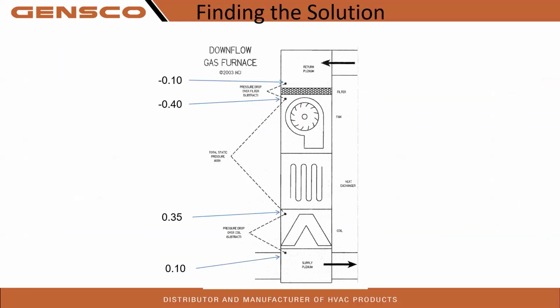Finding the solution. So we got a downflow gas furnace, right? So these are ideally what we want to see. So total external static pressure is 0.75. We could have symptoms, could be the coil freezing, your furnace is tripping limit. So we could see an iced up coil. We got a 0.35 right here and a 0.4 across the furnace. We're well over the 0.5. Sorry, I jumped the gun. I thought we were showing the ideal ones, but this is finding the solution. We got an issue, tripping limit switch here.